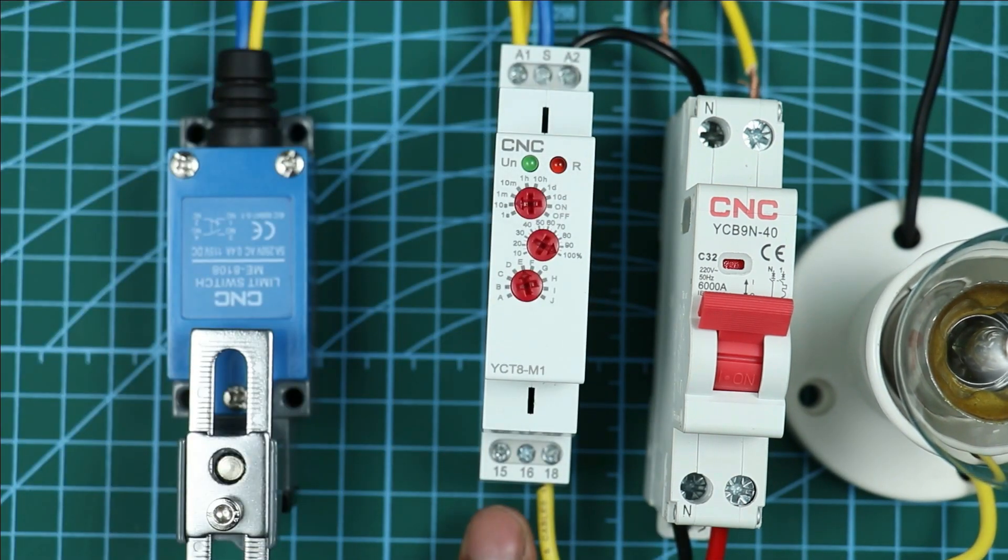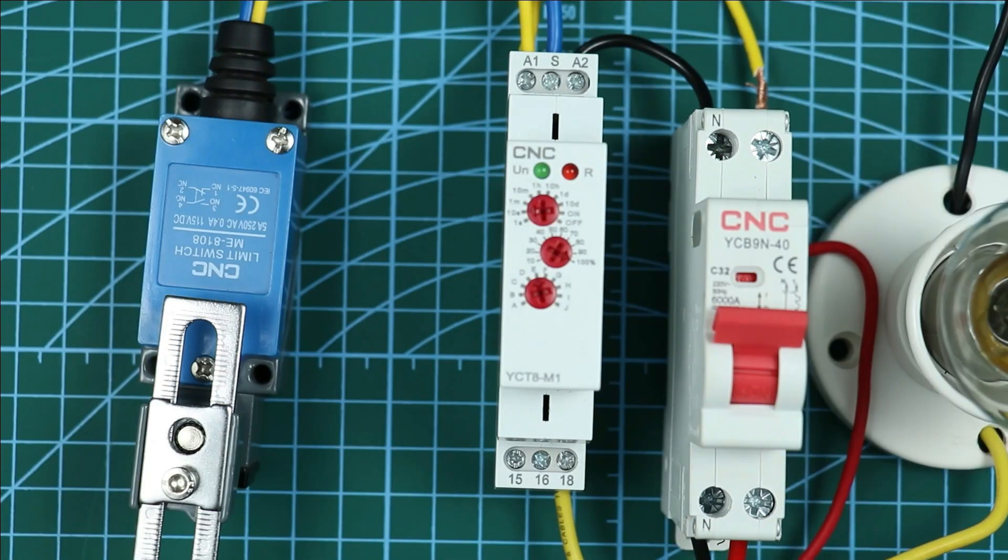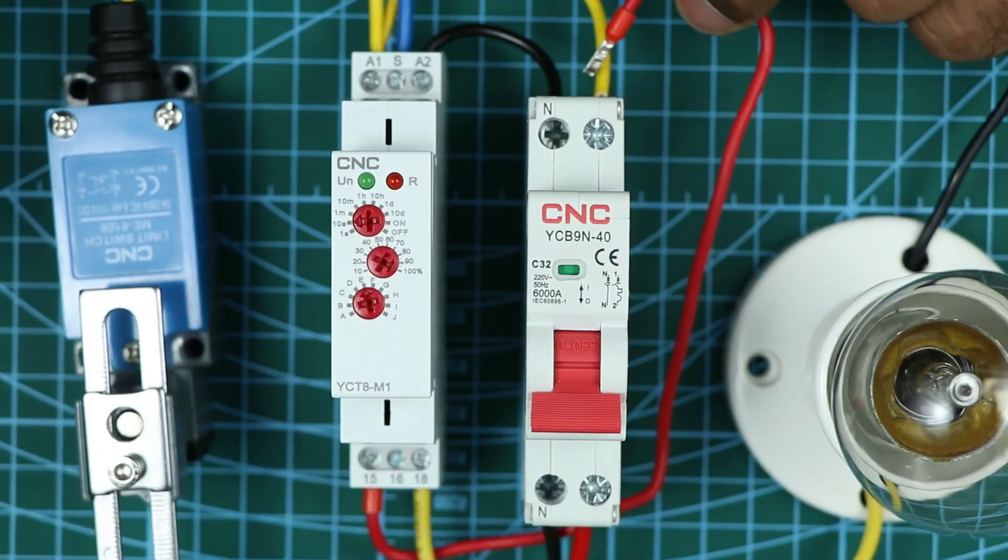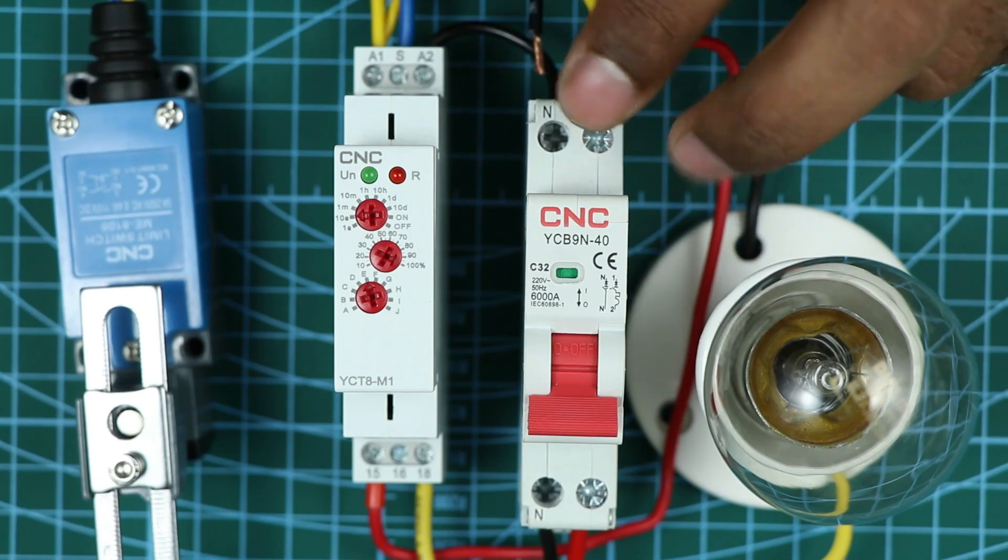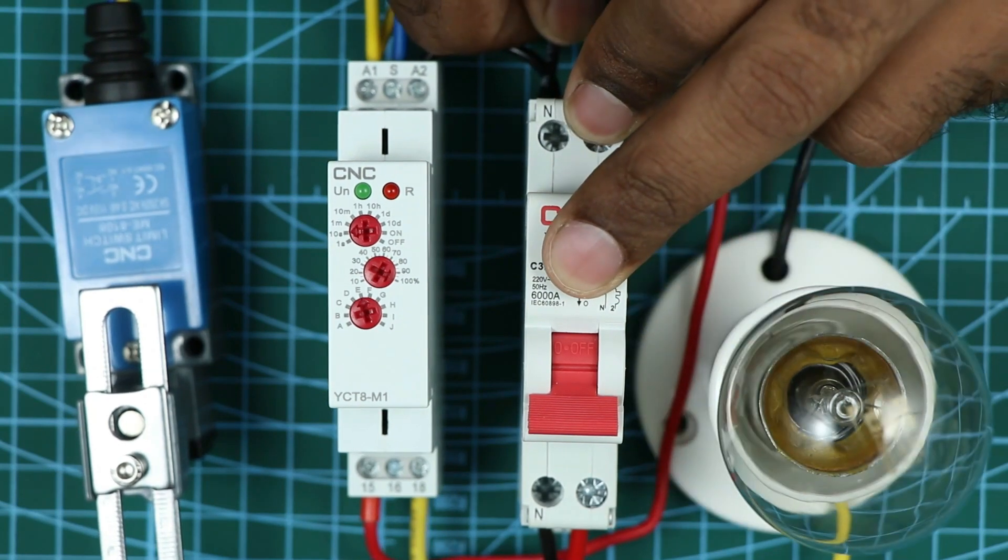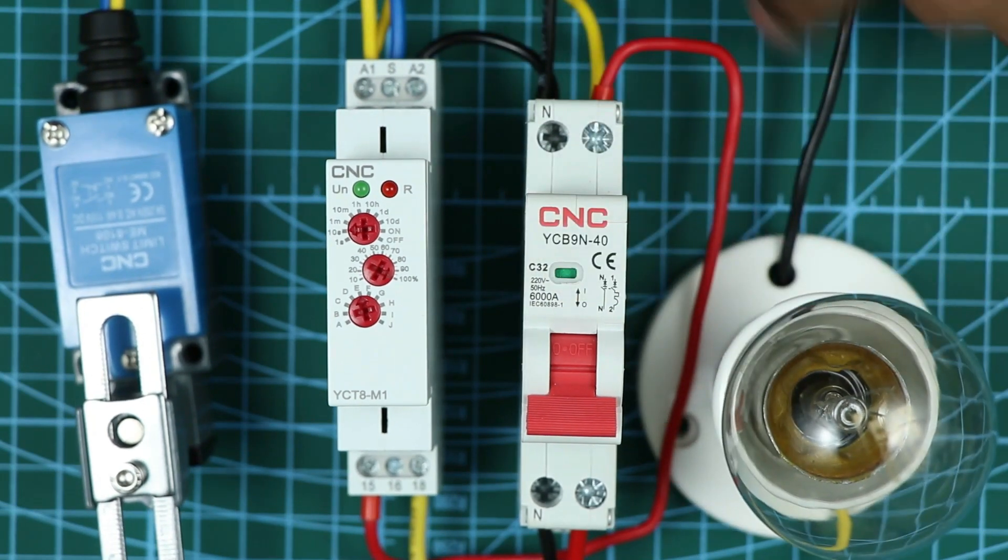At the common terminal of this timer, that is 15 number terminal, we have to provide phase supply. For this, I am taking one end of the wire and connecting to this 15 number terminal. Other end of the wire is to be connected with phase supply terminal of MCB. Take this neutral wire of the lamp and connect with neutral supply of the MCB so that through MCB, lamp receives neutral power supply.